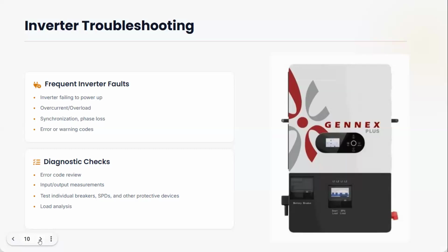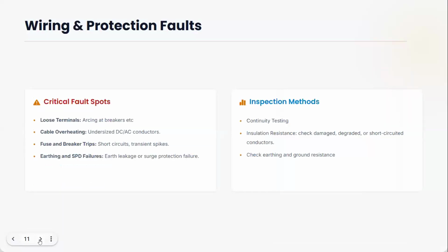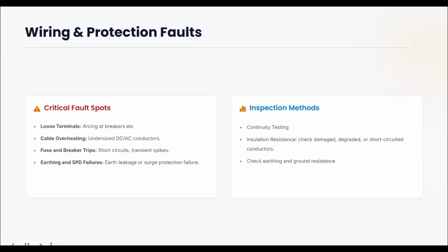Wiring and protection faults. This is very important as well. A critical fault spot is loose terminals. This has to do with how you handle terminals professionally, because if you don't tighten them properly, they will fail. Heating will set in, and when terminals are heating, they lead to breaker burning, and cables can start burning, which can lead to fire halfway. All these are interconnected, because the system is just a full connection of different components working together. So if one has issues, it's a headache to the system and to the installer, and eventually to the clients.